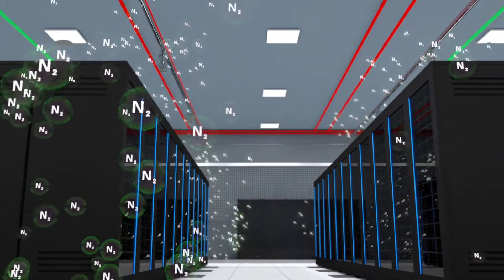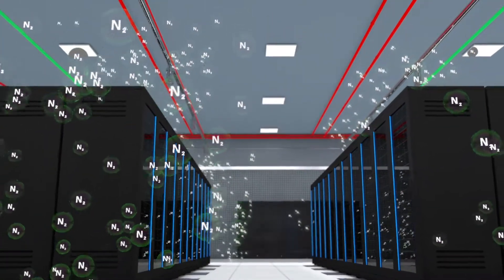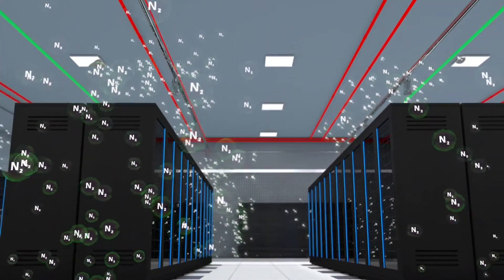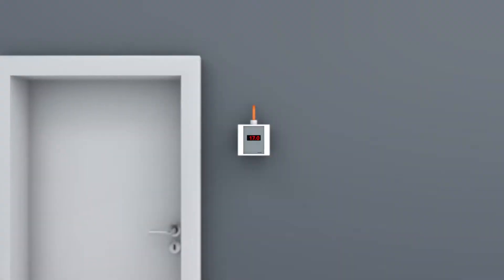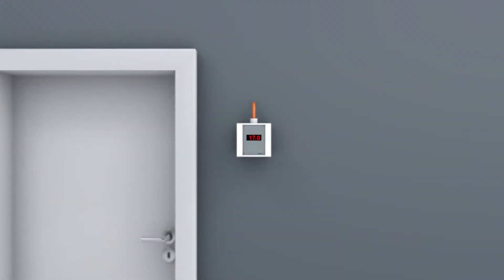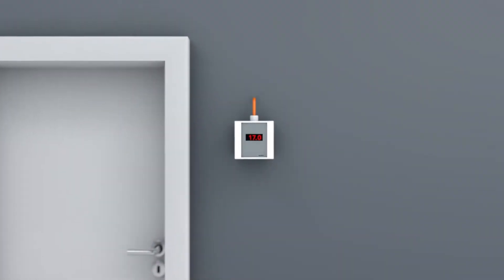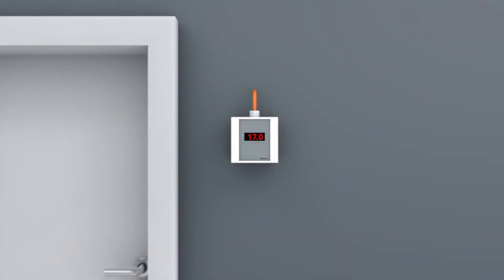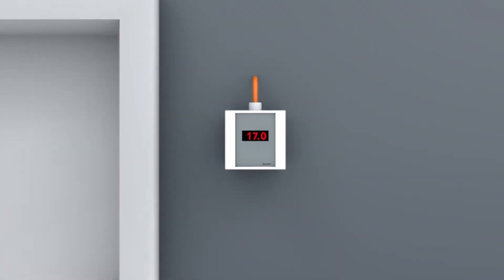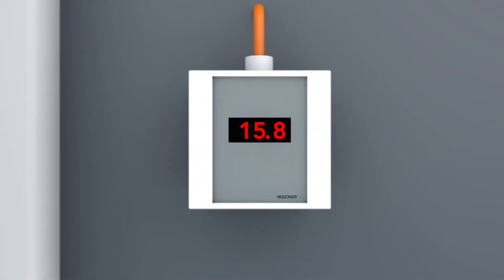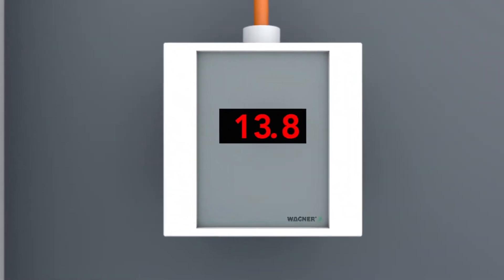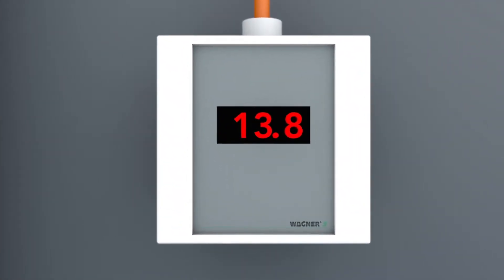When the oxygen level is this low, the fire cannot spread. The fire extinguishing system lowers the oxygen level from 17.0% by volume to 13.8% by volume.